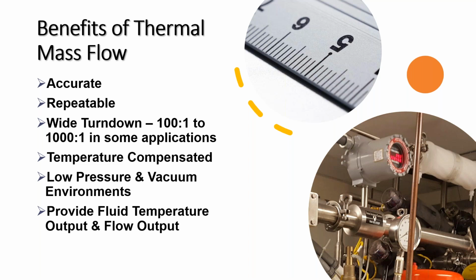The other benefit of thermal mass is that we're temperature compensated. So temperature changes are not really a problem for us. As long as we know where you're operating, where your mins and your maxes are, we set all that up during calibration. The other nice advantage of using thermal mass is that typically pressure is not a problem. Thermal mass is very good in low pressure, and it's very good in even vacuum environments. We really don't care so much about pressure from a measurement perspective, because as long as that fluid is passing by the sensor, whether it's being pushed or pulled, it's still taking heat away from that sensor.